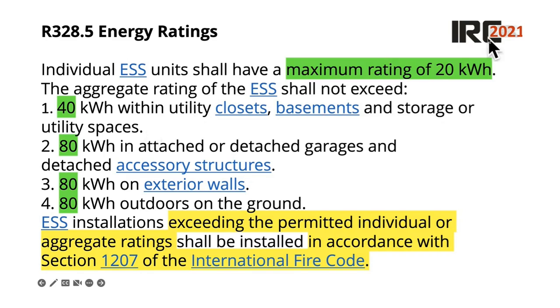And once again, we're looking at the IRC, so this is not commercial. And then what we have here is 80 kilowatt hours in attached or detached garages, 80 kilowatt hours on exterior walls, and 80 kilowatt hours outdoors on the ground. And so at first you might say, well, what if I'm a billionaire? Why can't I do this? And so of course you could do large scale fire testing, go by the International Fire Code, section 1207, and you can put a megawatt battery there, just like utility scale.